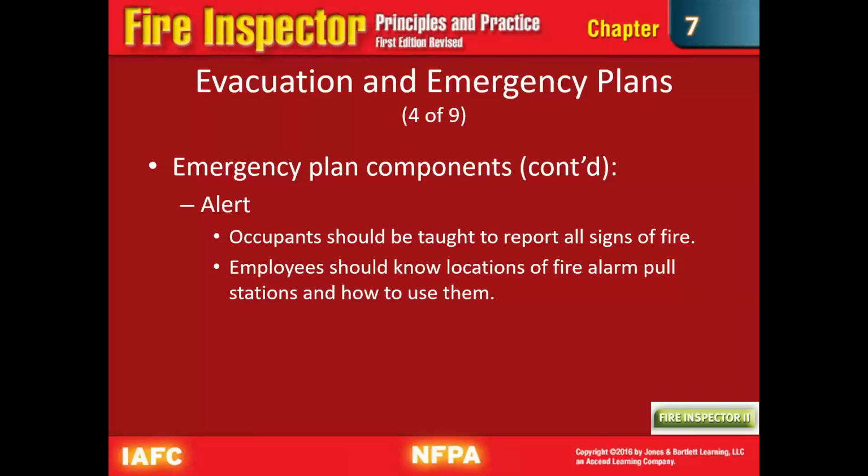Well, the problem is there was an incident. They go and they pull the protection box, and it makes a loud buzzing noise, but it does not set off the alarm. So you need to be educated on what your system is and how it works and how to activate that system. So all they did was mess with the tamper box. They didn't activate the system, and luckily it was a false alarm and everything was okay. But that's where education comes in, and we need to make sure that these places are functioning and doing these things properly.